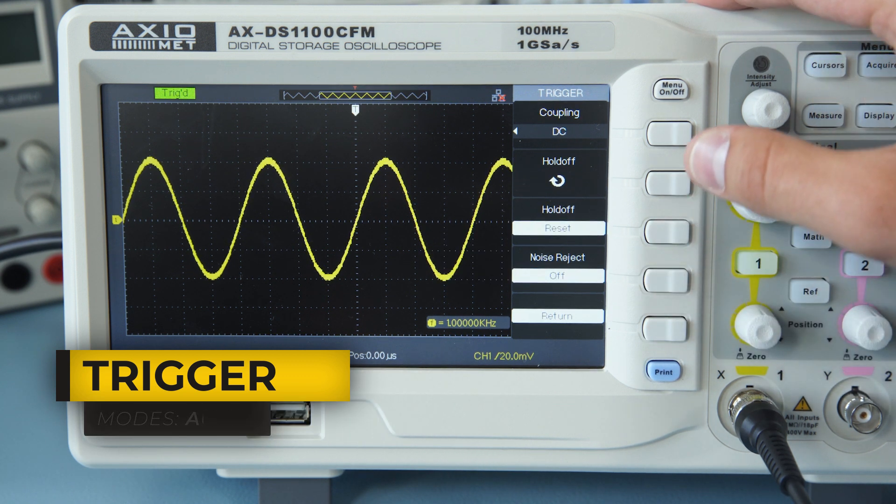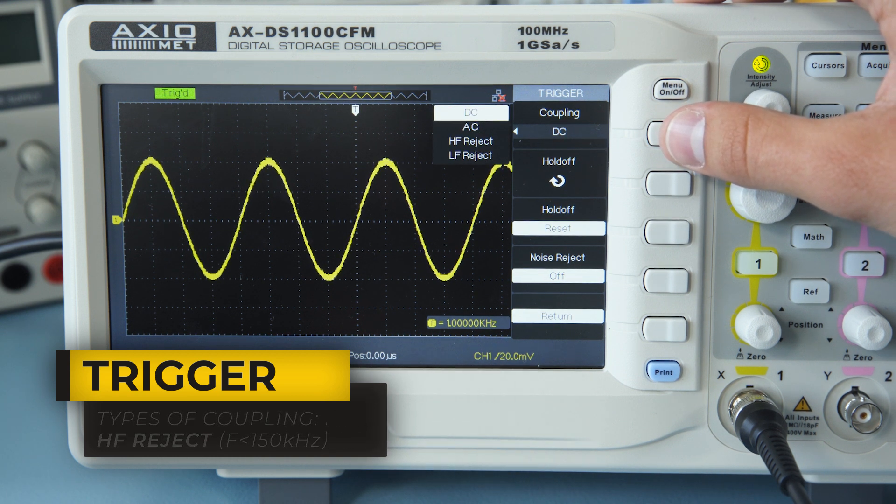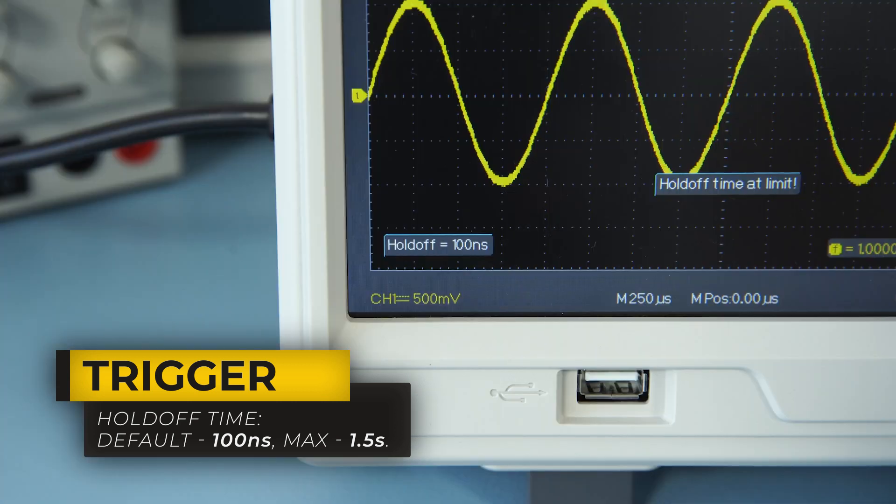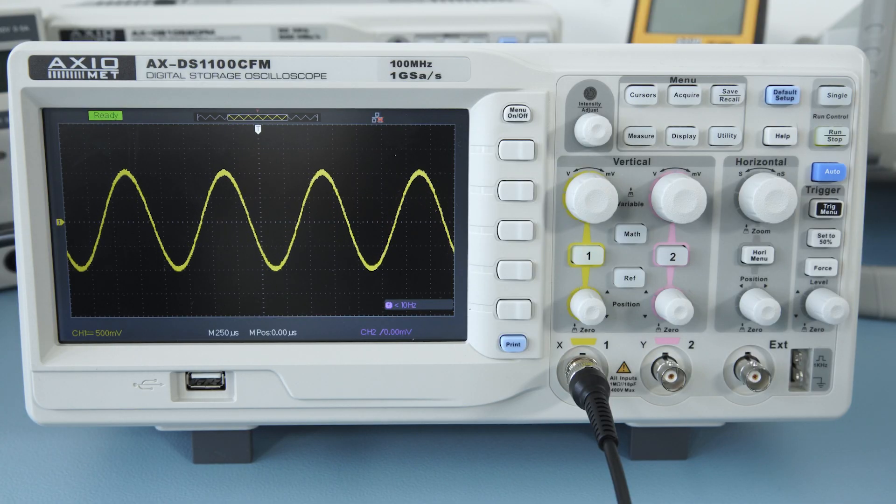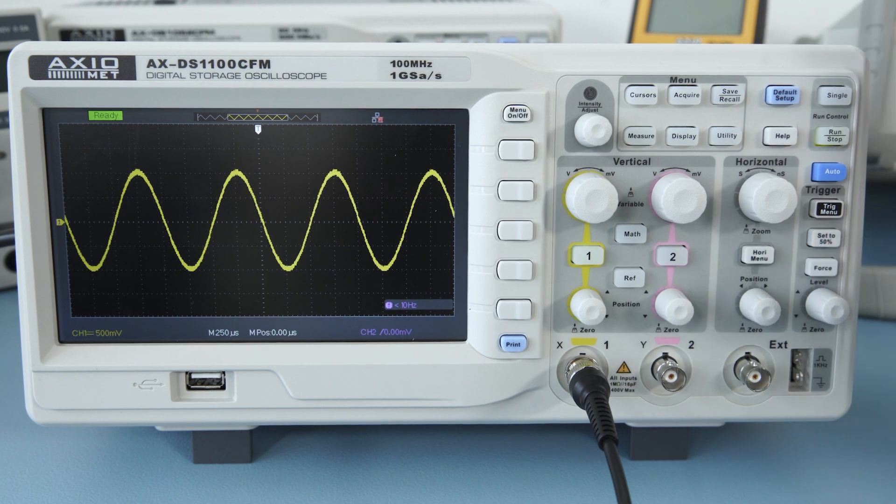In the trigger setup menu, you can define the type of coupling or change the holdoff time in case of complex waveforms. Turn on the Noise Reject function to reduce the possibility of noise coming from the trigger.